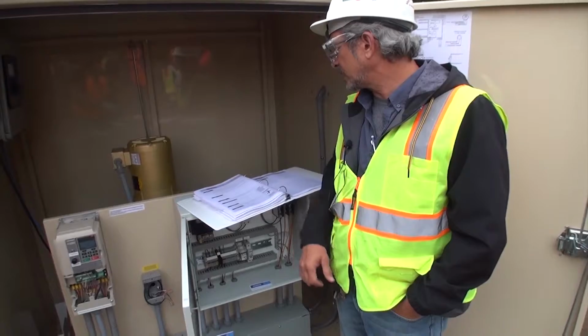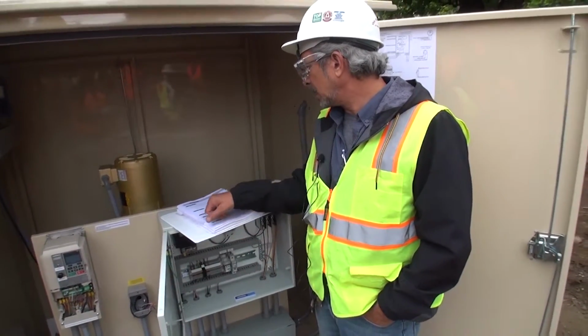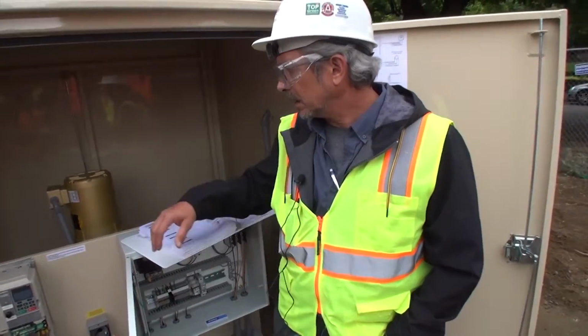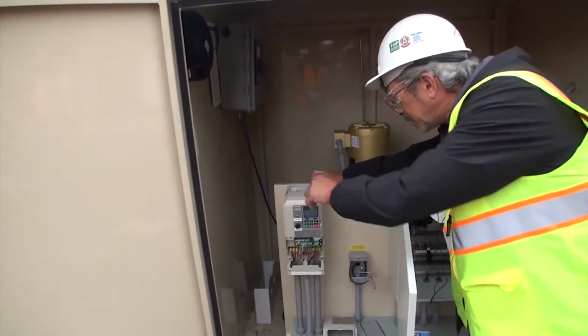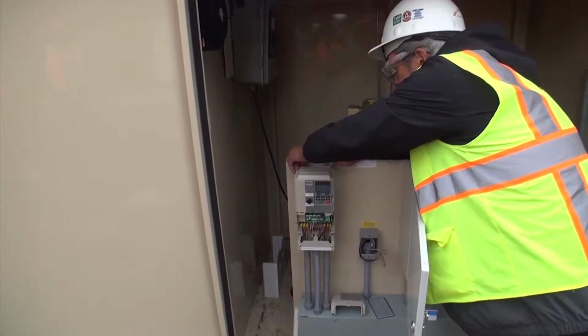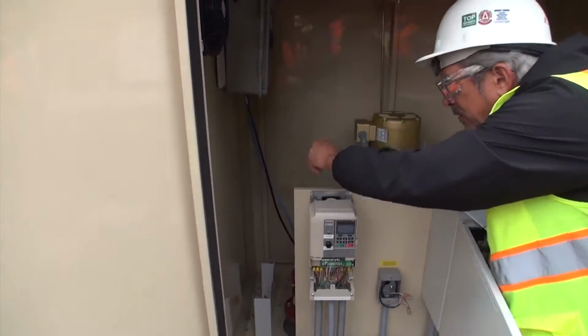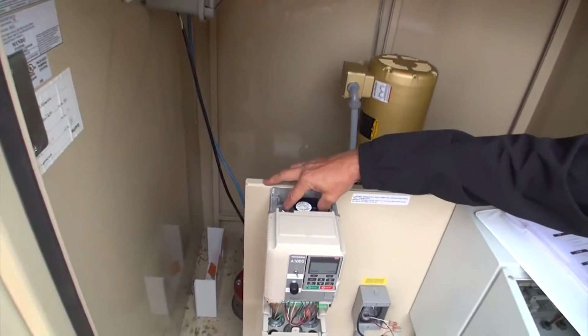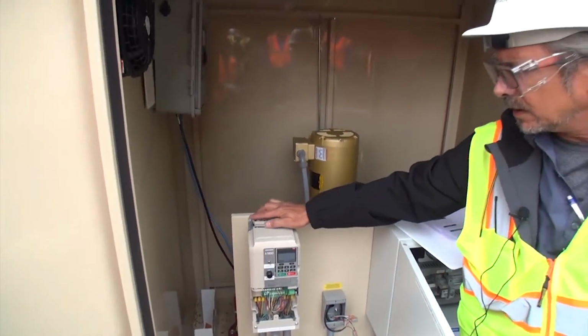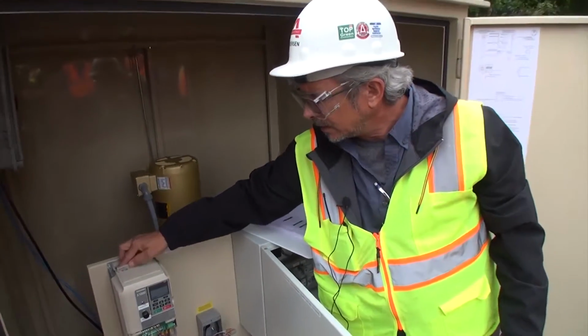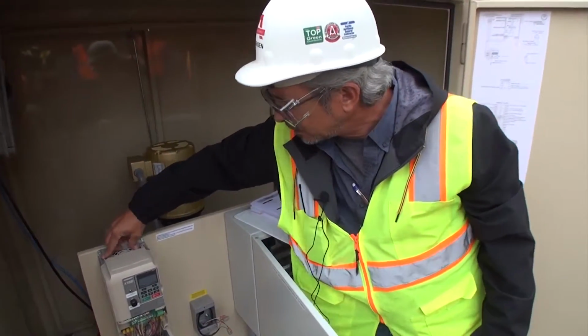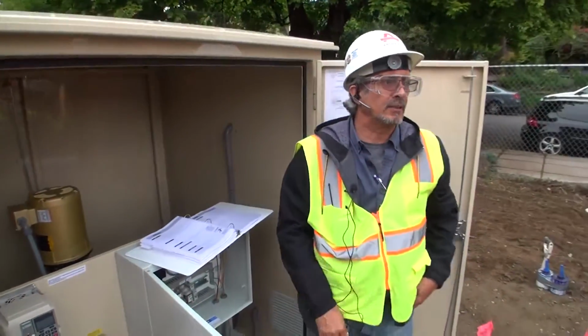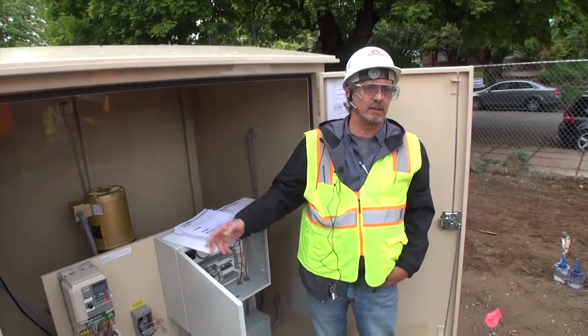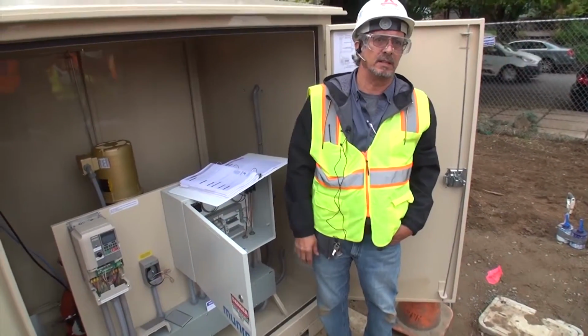We don't have level sensors here. We go to the VFD. Again, there's a fan here. If you have to replace it, you just pop this off. Takes no tools. Take the fan out, change it, but you want to make sure that that works. If that is not working, this drive will fault on overheat, over temp. And if you have to temporarily, you can actually put a fan on there underneath blowing through that, and that'll keep it running until you get another fan for it.